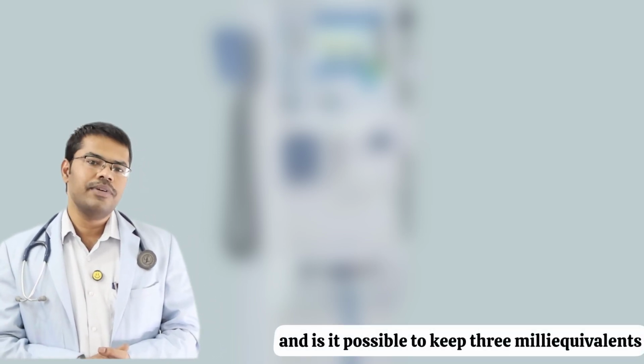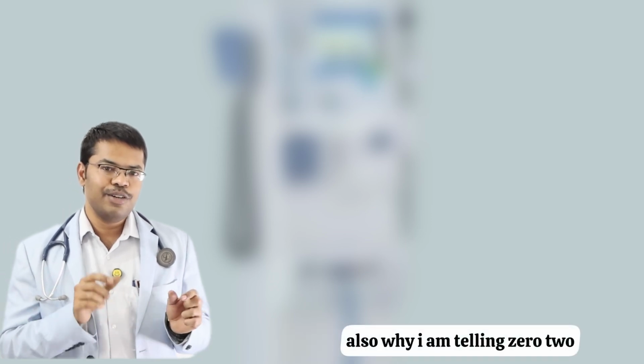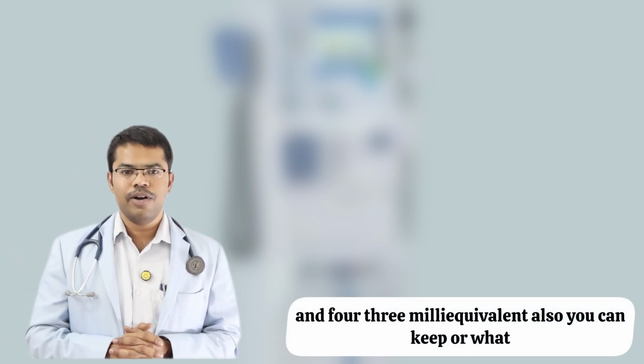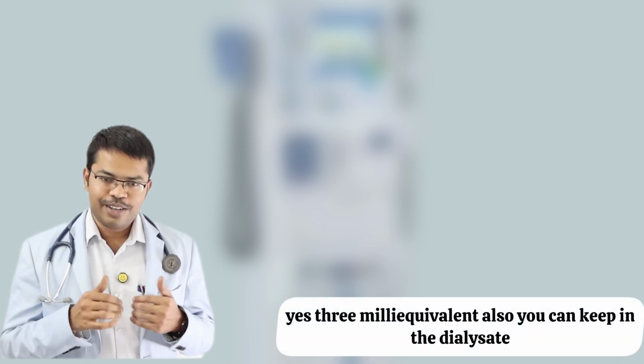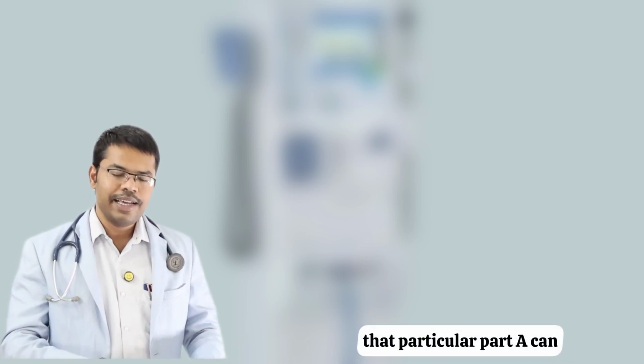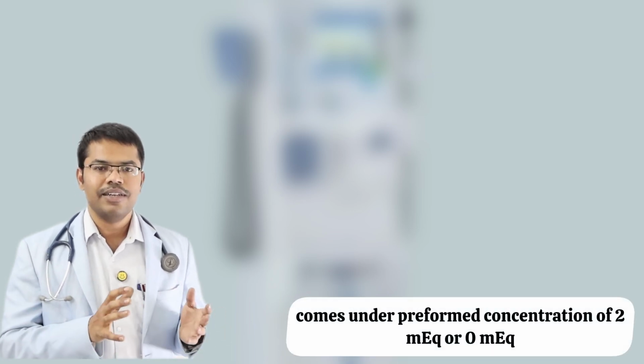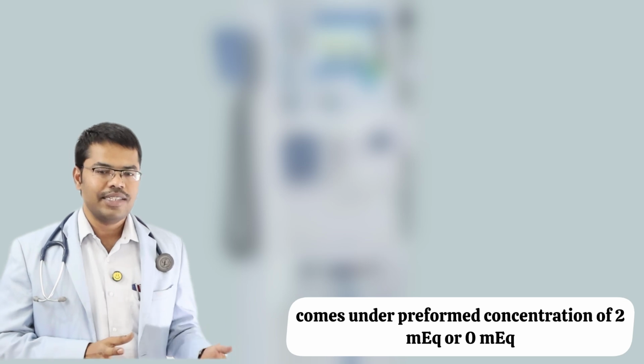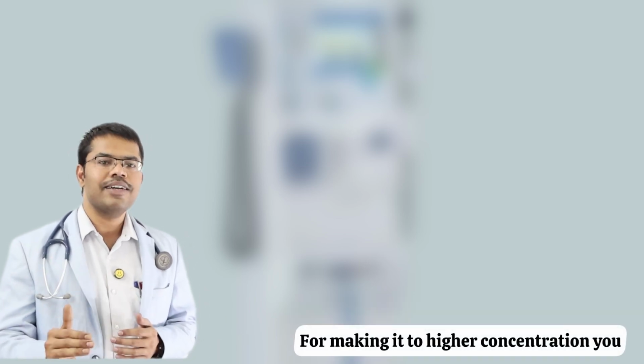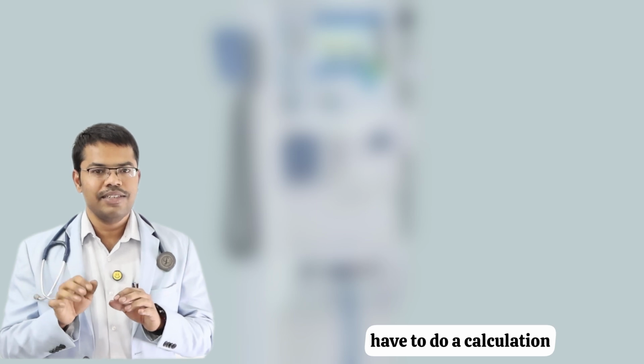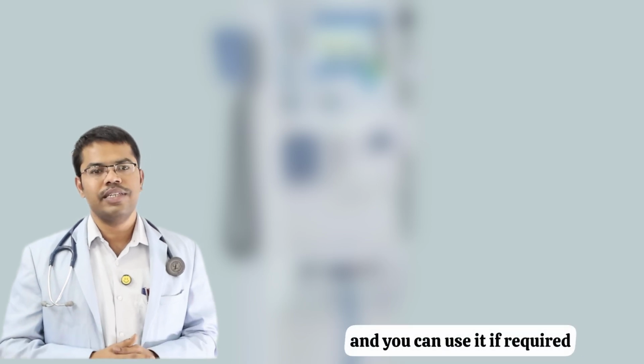Is it possible to keep 3 milliequivalent also? Why am I telling 0, 2 and 4? Yes, 3 milliequivalent also you can keep in the dialysate. But the problem is that the part A can which is available comes in preformed concentrations of 2 milliequivalent or 0 milliequivalent. For making it a higher concentration, you have to do a calculation, which I already told, there is a video. You have to increase it to 3 or 4. You can train the technologist, or you can prepare a can in advance and use it if required.